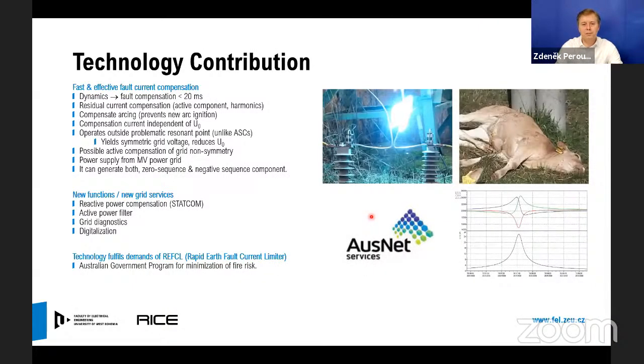The technology contribution. So we offer by our idea and our device very fast and effective fault current compensation. The dynamics is excellent. The fault is compensated below 20 milliseconds. We are able to secure the full zero residual current. It means that we are able to fully compensate the fault current, including the active fault current component as well as higher harmonics in the fault current. We are able to compensate the arcing. And by special control interventions, we are able to prevent new arc ignitions.